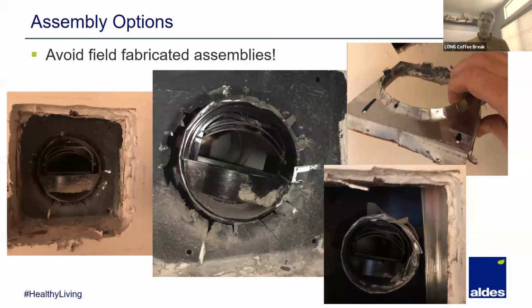Some mechanics I'd suggest to a specifying engineer: in your specifications, list both and the particulars of each. I'd petition to have a schedule showing both, with notes saying make sure you apply the right one to the right location and static pressure. Then through the submittal process, the rep and your comments can say, I'm not going to tell you exactly where the high and low pressures go, but you need to put the right ones in the right space. That would help a specifying engineer.